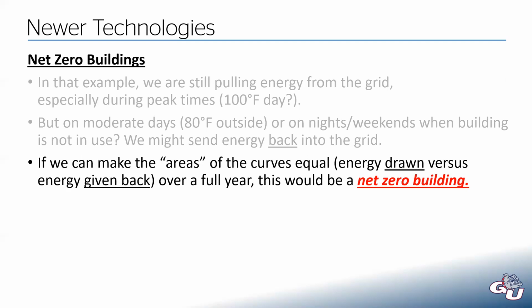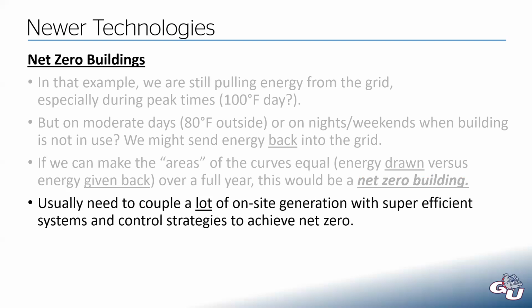Not a zero energy building, because there's still many hours where we're in the negative and pulling energy from the utility, but maybe over a year we can even those out, make it average out so that it's zero or below zero. Usually you need to have a lot of on-site generation to do that and have super efficient systems and have the control strategies to achieve net zero. So there are some control strategies that the energy code says, well, we're not going to make you do that because it's a lot of hassle and maybe doesn't save as much energy as some of the more essential control strategies. Well, if we're trying to achieve this net zero building, we have to pull out all of the stops and save every kilowatt hour we can.